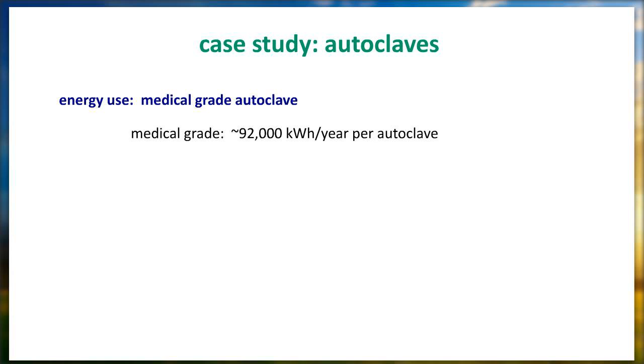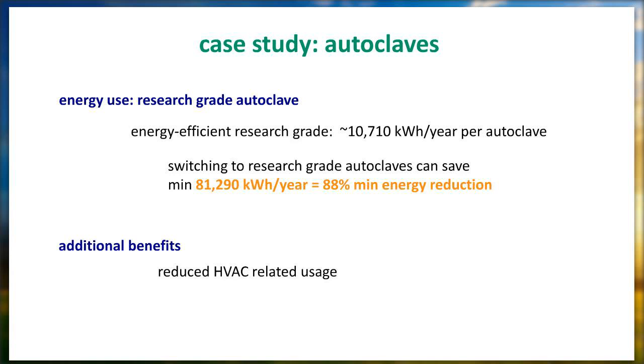If we were to instead not use medical grade autoclaves, but use something called a research grade autoclave, these use about 11,000 kilowatt hours per year, representing almost 90% energy reduction, just by switching to a more appropriate size for the work that's being done in the environment. And again, this is really looking specifically at plug load and steam generation, not at any of the effects it might have on HVAC, which is listed under the additional benefits.